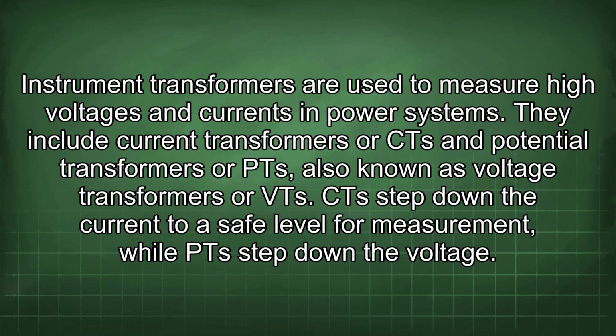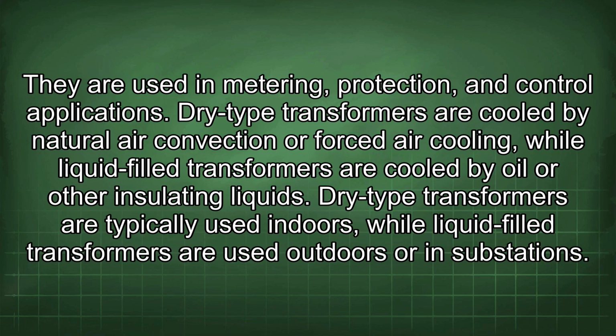Instrument transformers are used to measure high voltages and currents in power systems. They include current transformers or CT and potential transformers or PT, also known as voltage transformers or VT. CT step down the current to a safe level for measurement, while PT step down the voltage. They are used in metering, protection, and control applications.